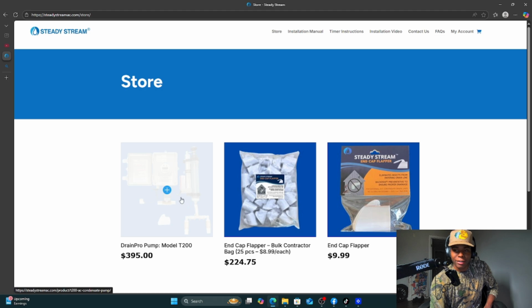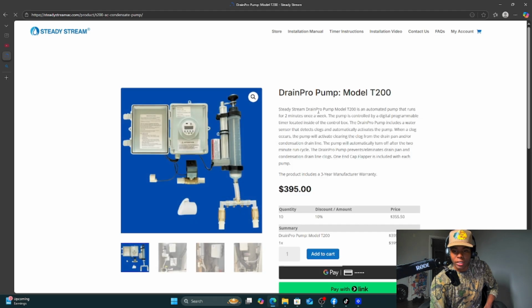Let's look at this thing right here. Steady stream drain pump pro model T200, automatic pump that runs for 2 minutes once a week. The pump is controlled by a digital programmable timer located inside a control box. The drain pump includes a water sensor that detects clogs and automatically activates the pump. When a clog occurs, the pump will activate, clearing the clog from the drain pan or condensation line. The pump will automatically turn off after a 2-minute run cycle. The drain pump prevents and eliminates drain pan and condensation drain line clogs.